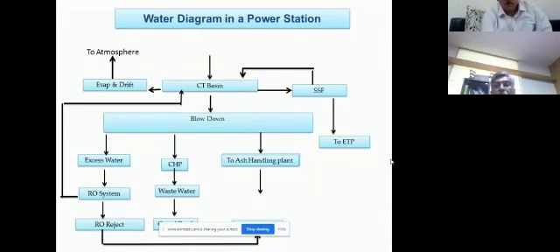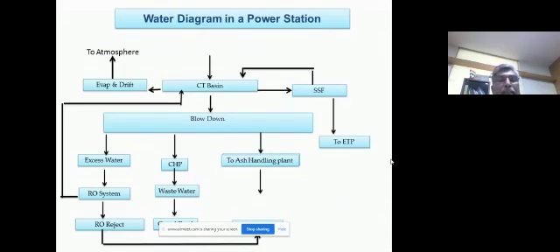So this is the way the water is utilized. And you see the water which is required is only for the evaporation and drift loss and the blow down, and this is the water which is required as makeup water. Beyond this, everything we have controlled. From the evaporation drift, it goes from the cooling tower basin to the side stream filter, and from there to the ETP. And the blow down water we are directly taking for the ash handling, and the excess water is going to the RO system, the RO reject, and then it is recycled back.